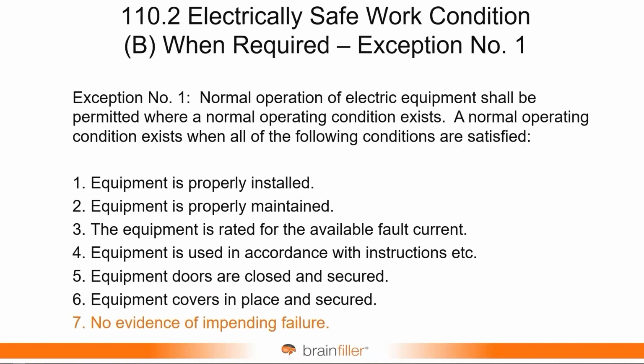Going back to our now 7 items that we check, the 7 conditions: no evidence of impending failure. This is one that still will sometimes have people scratching their head, like, how do I know if there's a possibility of this failing or not? Well, there's a lot of judgment that goes into it. And I always use the famous phrase, if you see something, say something, meaning if the equipment is buzzing or it's unusually hot or just something obvious that doesn't seem right, well, check into it. I don't think you can check that box.